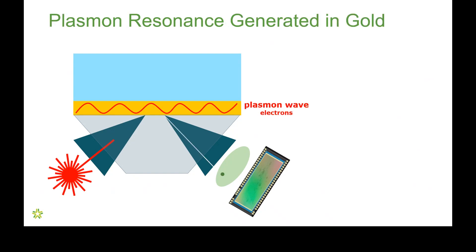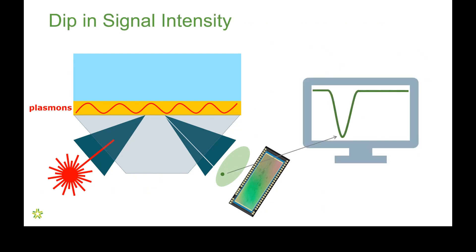But what actually happens is that at one particular angle, the light is converted into a plasmon wave, a wave of electrons that resonates through that gold layer. So, the angle at which this happens is not reflected to the detector. Instead, it produces a dark spot across that range of angles. And that dark spot, when you plot it as intensity versus angle, produces a dip.